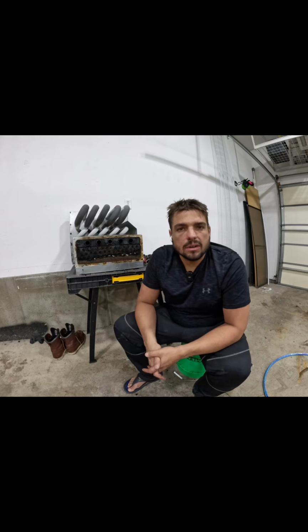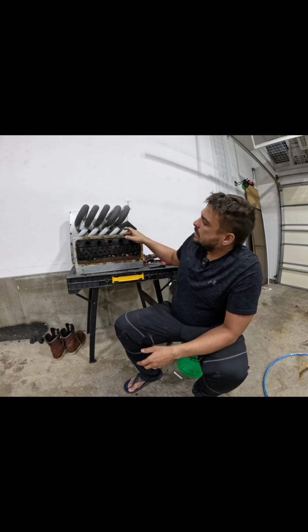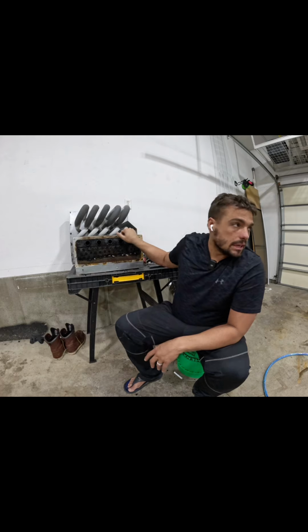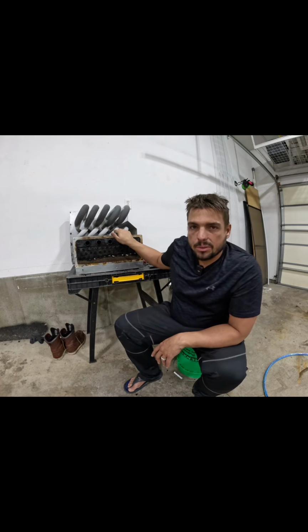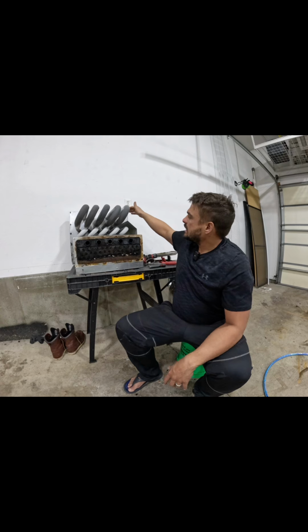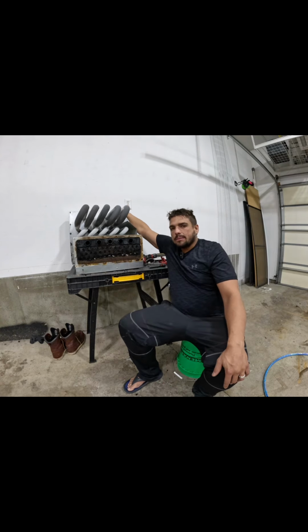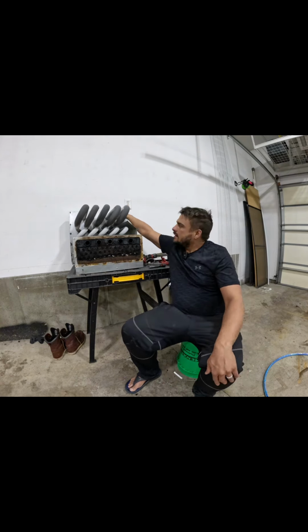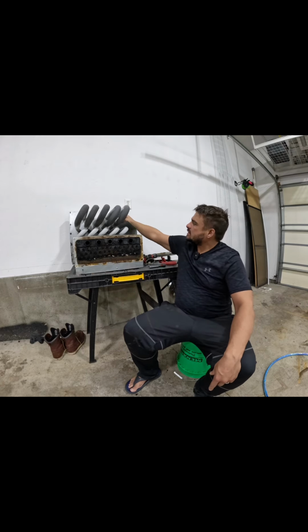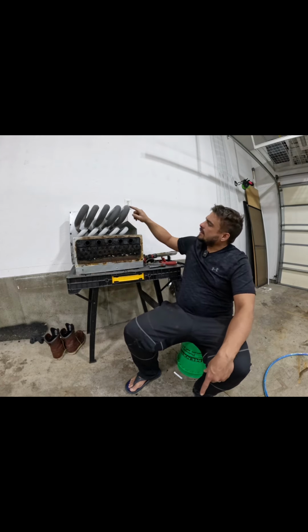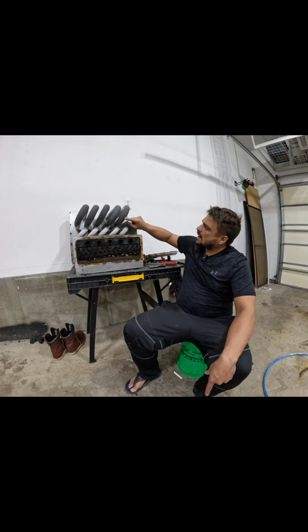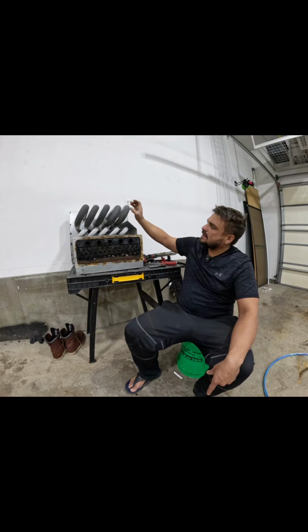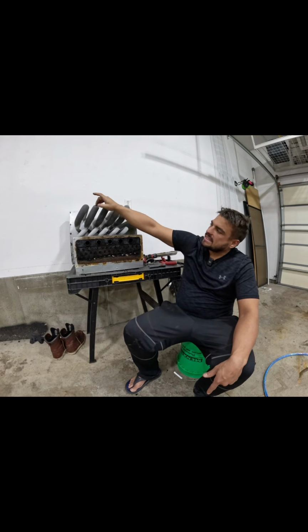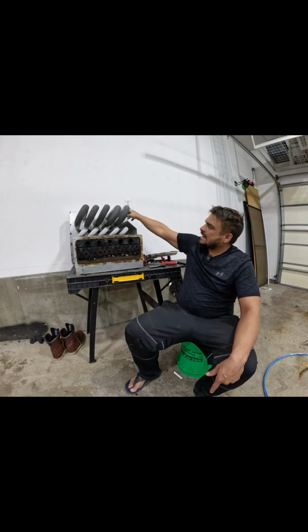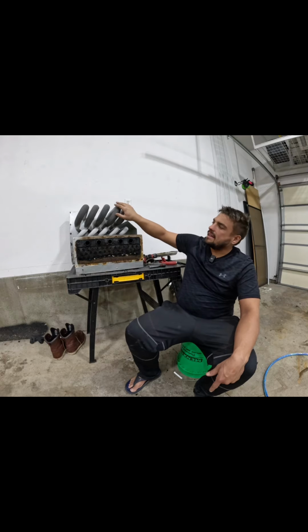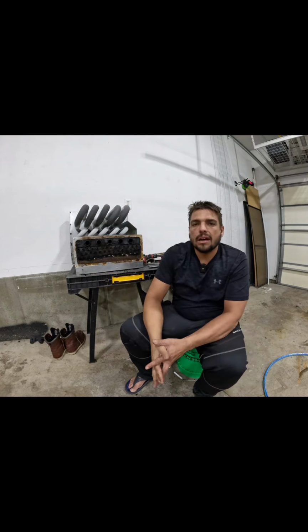Or you replace the furnace. Those are the two options. This particular unit was tripping its rollout switches, and I have a furnace in the garage that'll show you where the rollout switch is. Tripping the rollout switches means the temperature up in the burn chamber we were looking at before was getting hot. Basically that flame wasn't traveling down. If this tube was clear and you were watching the flame, it would darn near get to this bend. In fact, this is probably the hottest part of the heat exchanger because that flame is hitting the end of these. I've seen it where if the flame isn't set properly, these get red hot, and they can actually erode to nothing from the flame.